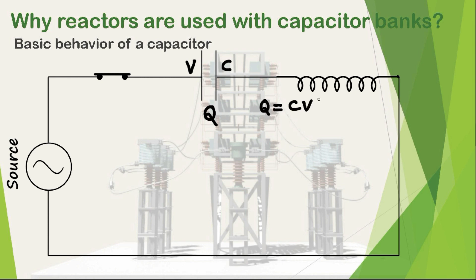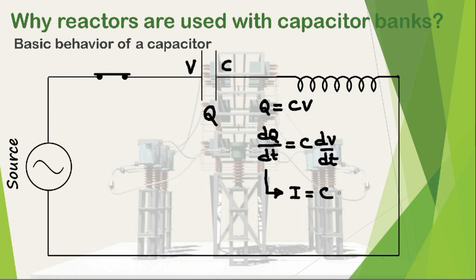If we differentiate both sides of this equation, we will get dQ/dt equals C times dV/dt. Now, what is dQ/dt? dQ/dt is nothing but current. So we can write current I equals C times dV/dt. This I is nothing but the current flowing through the capacitor bank during switching on, and this is called the charging current of the capacitor.